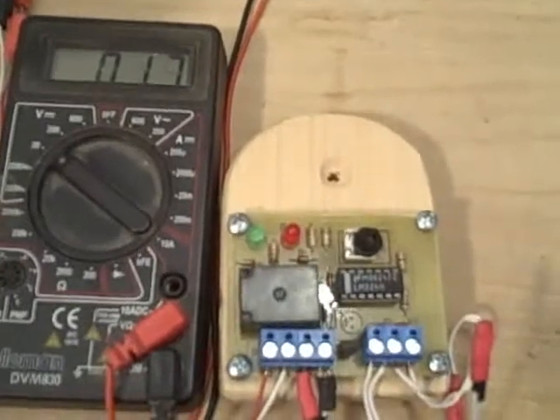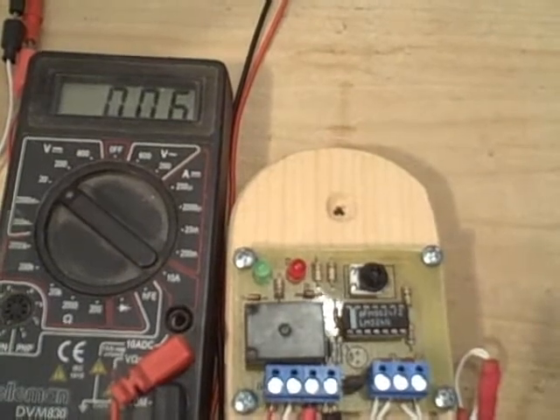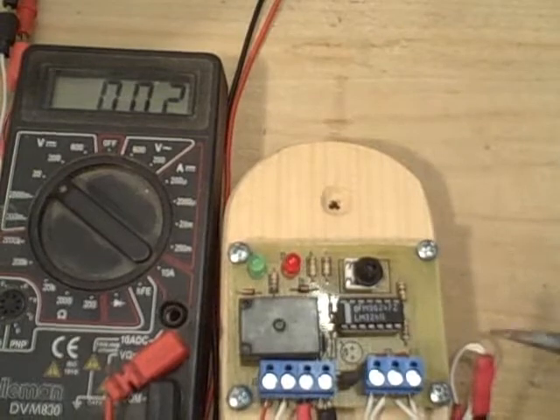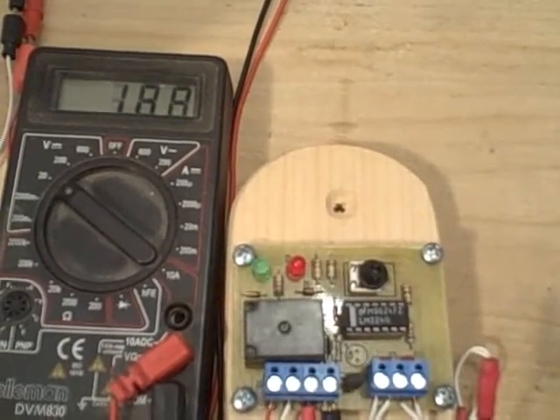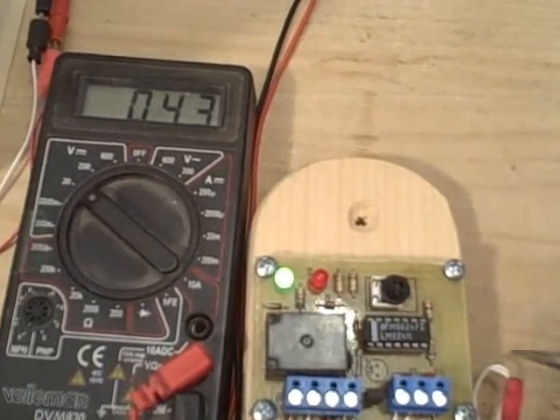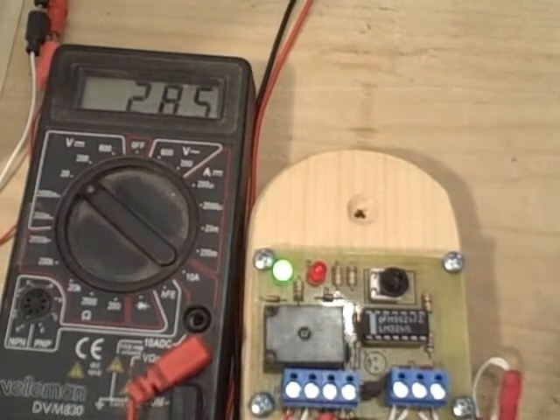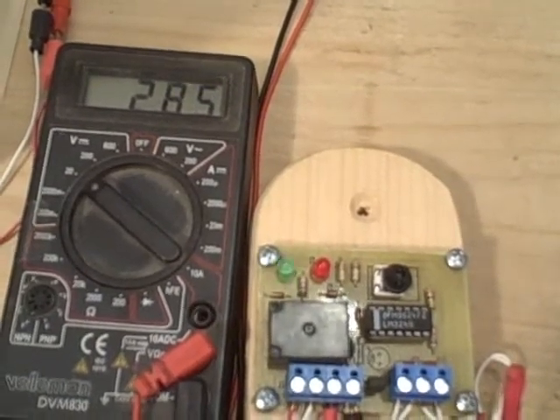Now, with the pump connected, let's see if we can activate the controller and try it again. Add a little heat to the collector thermistor. The pump tries to turn on. The voltage went up a little, but that's not very high, 22.8 volts. What you heard is chatter. That's the pump coming on and off.